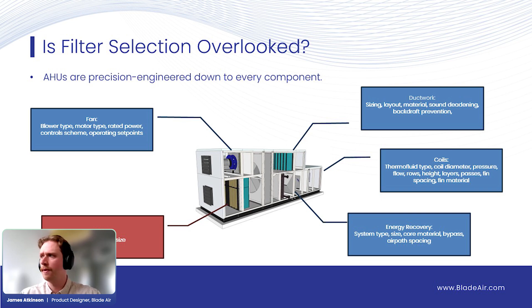We also don't monitor them as much as other systems, right? So your fans, your coil, all have many data points that are tracked by a building automation system to make sure that your air handling system is working as it's designed to. Now, filters don't have that. Usually there's just one, maybe, just a pressure drop, a simple, basically calculation or comparison of the upstream static pressure and the downstream static pressure. And we use that to check, is the filter too loaded? Am I overloading the fans? But it doesn't actually show your performance. It doesn't actually tell you if you're filtering air.